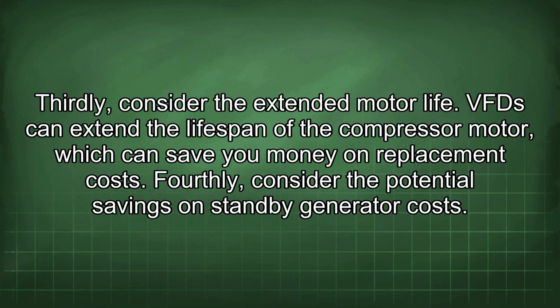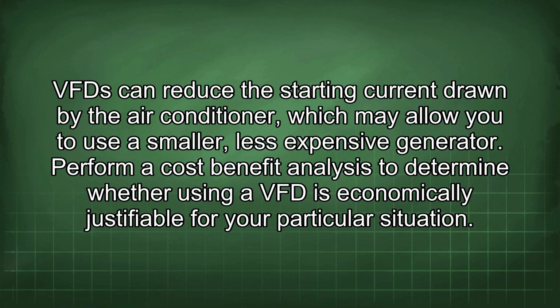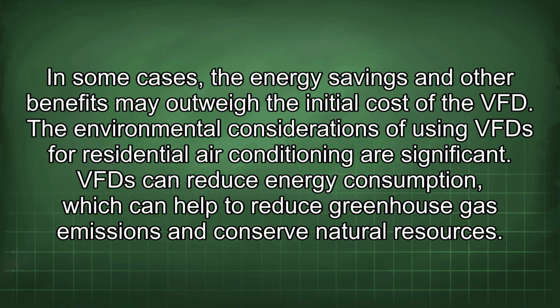Thirdly, consider the extended motor life. VFDs can extend the lifespan of the compressor motor, which can save you money on replacement costs. Fourthly, consider the potential savings on standby generator cost. VFDs can reduce the starting current drawn by the air conditioner, which may allow you to use a smaller, less expensive generator. Perform a cost-benefit analysis to determine whether using a VFD is economically justifiable for your particular situation. In some cases, the energy savings and other benefits may outweigh the initial cost of the VFD.